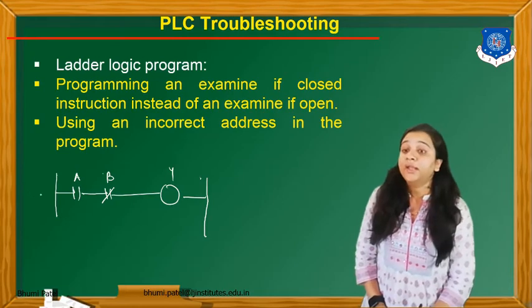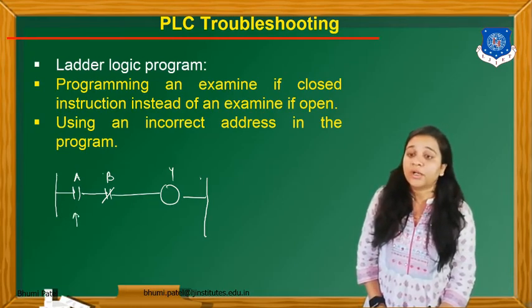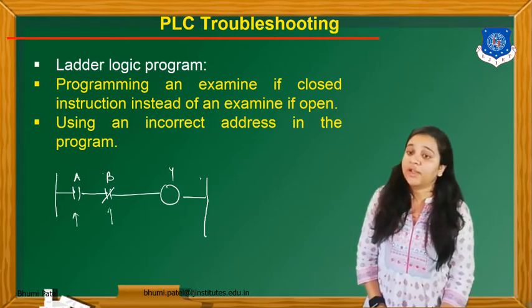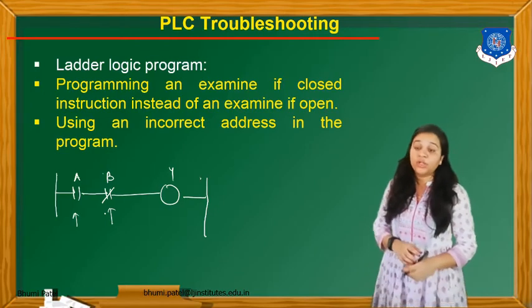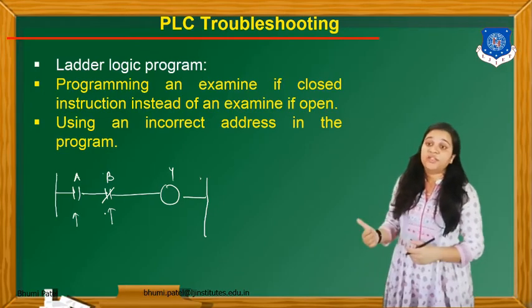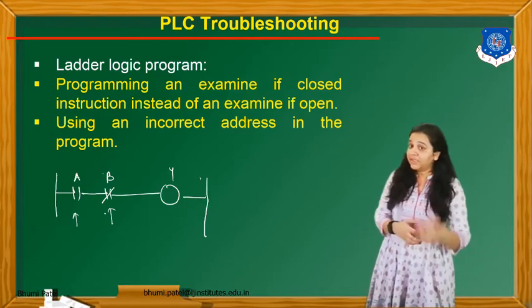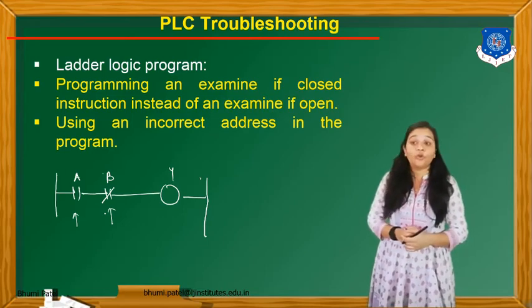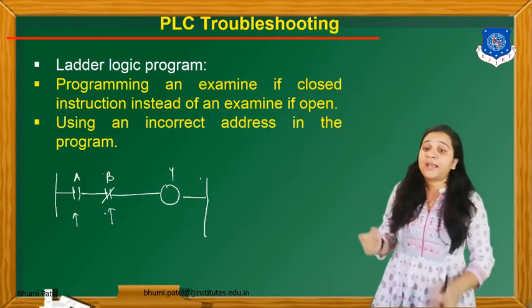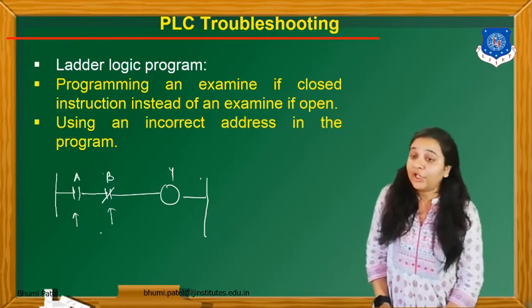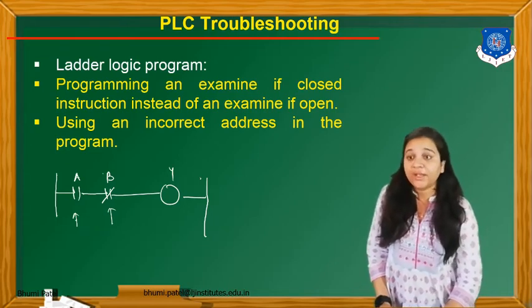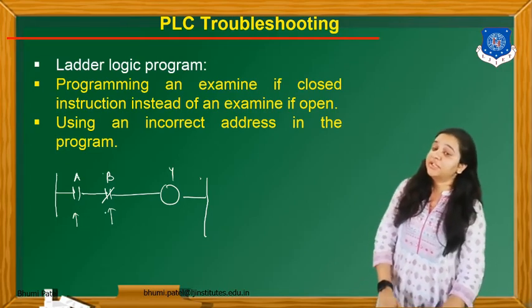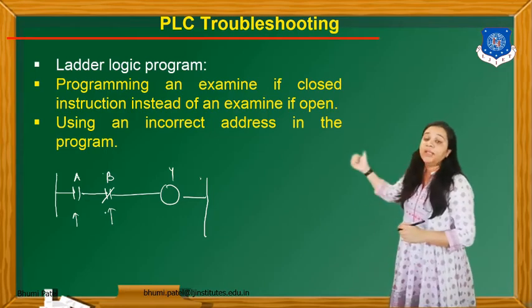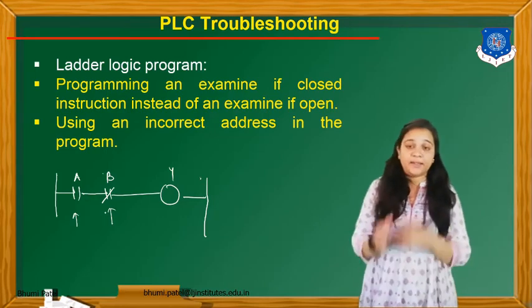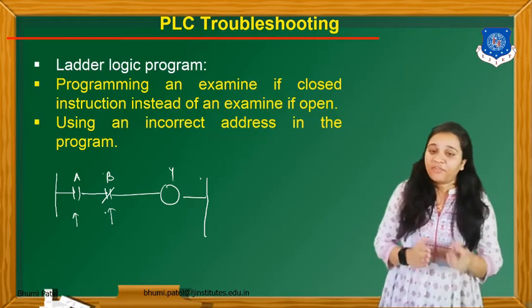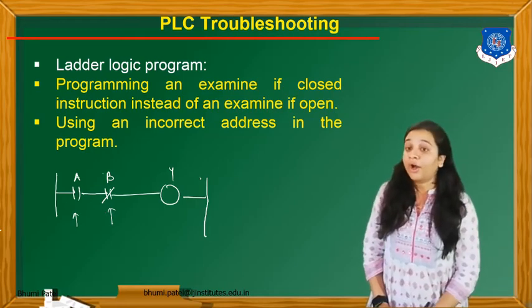So for that, here we can connect one push button or a float switch, and here also we can connect a push button or a float switch. One switch is a normally open contact and the other switch is a normally closed contact. Both functions are inverse, so we have to continuously examine whether the open and close instructions executed in the ladder logic diagram perform perfectly in the hardware or not.